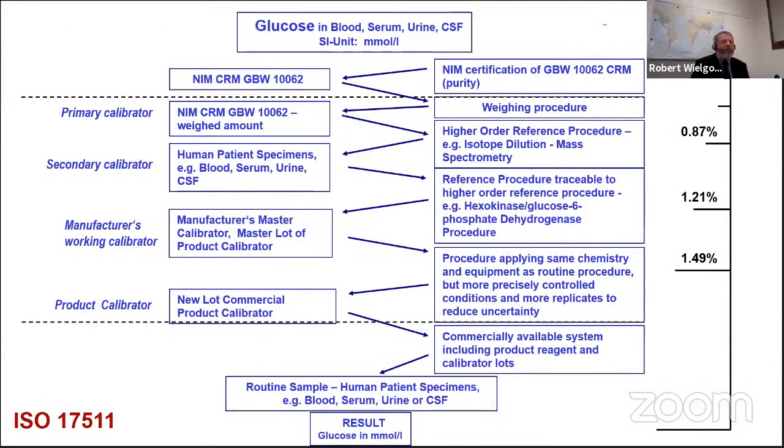So this is how a calibration or traceability scheme looks for glucose, which is the simplest of the measurands, starting with a pure material, moving to a reference method to measure glucose in serum, and then being able to apply that glucose in serum method and material within the industrial IVD systems to produce more calibrators for the patient measurement.